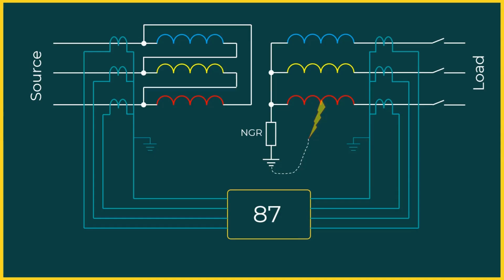It was expected the differential relay would act immediately, but it did not. The fault persisted, the NGR overheated, and it failed. Eventually, the neutral became effectively solidly grounded, and only then did the differential relay operate. By that time, the transformer had already experienced stress and the NGR was damaged.